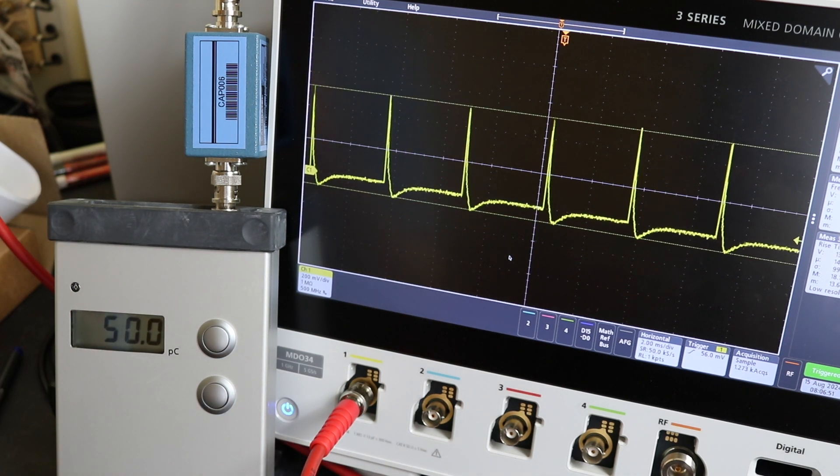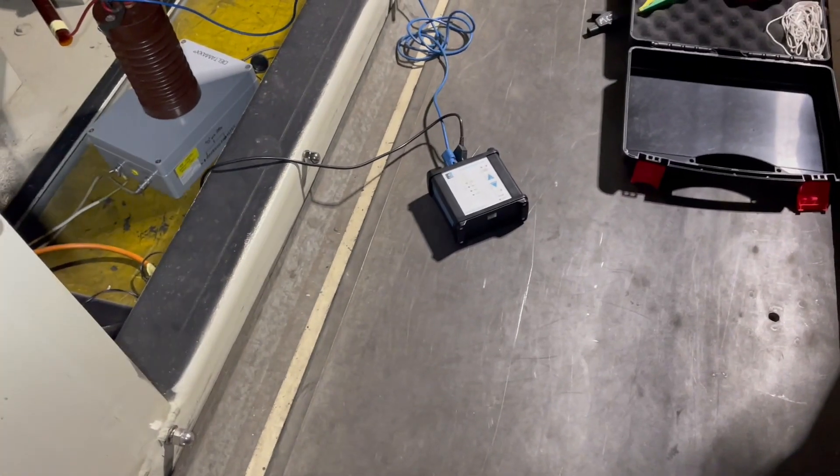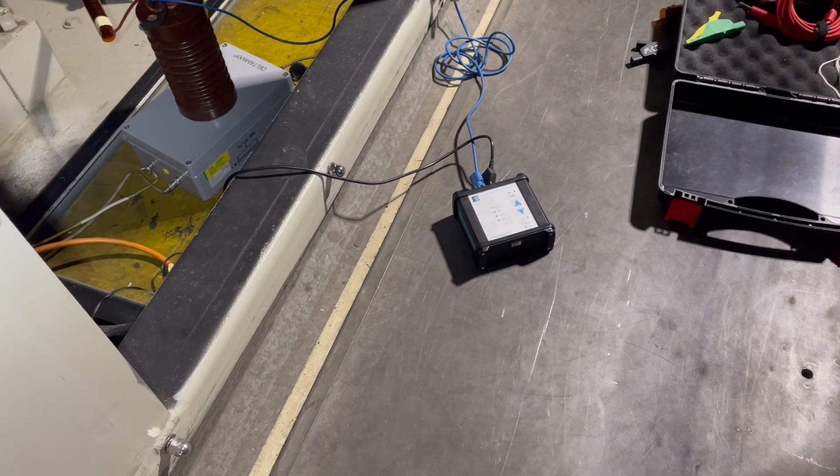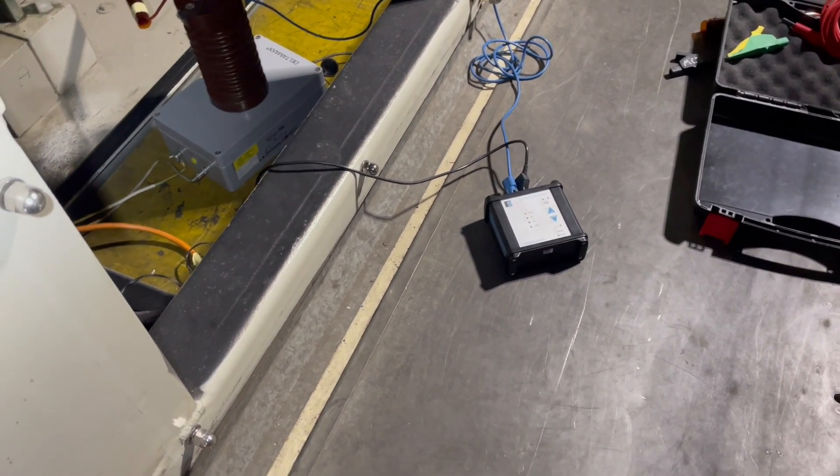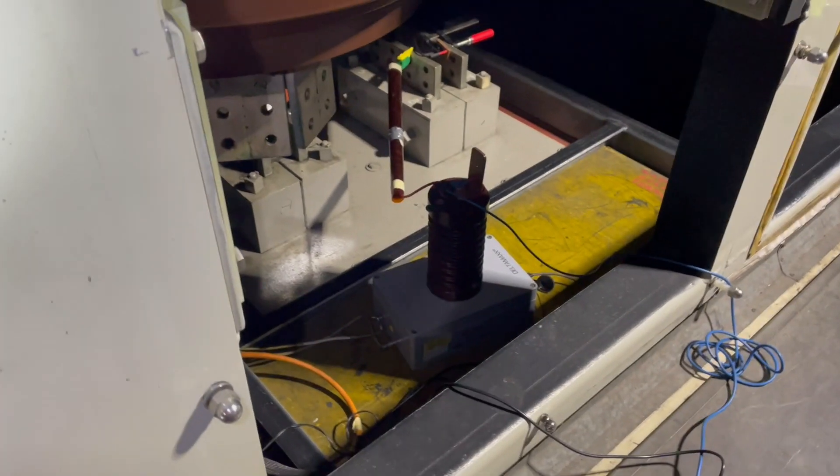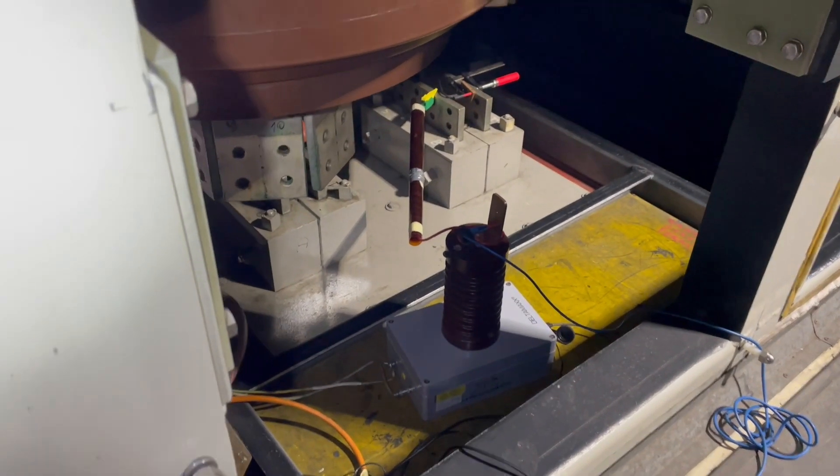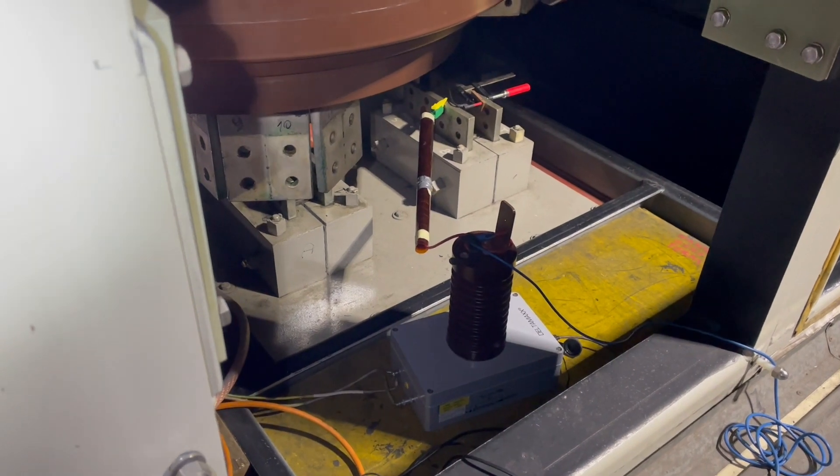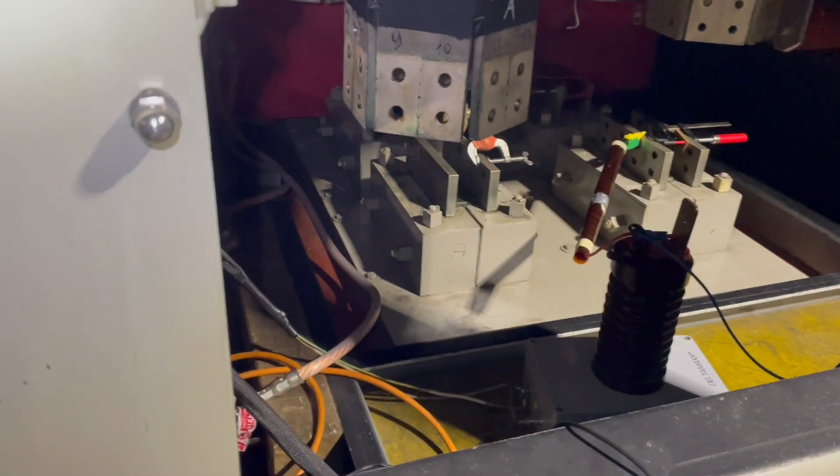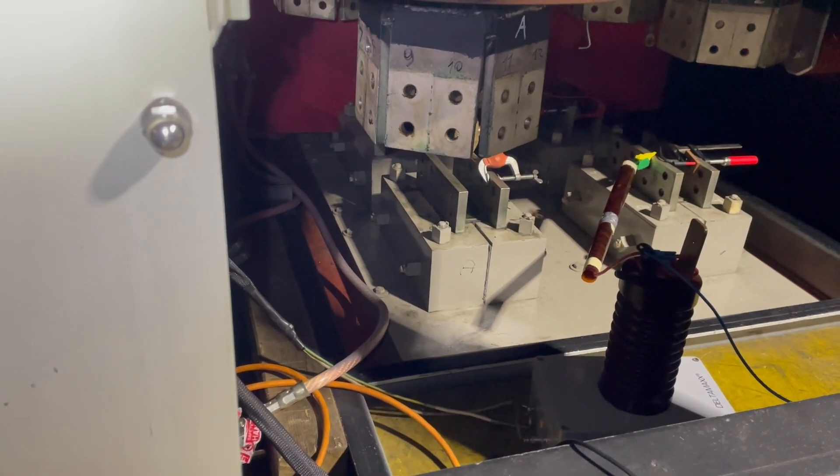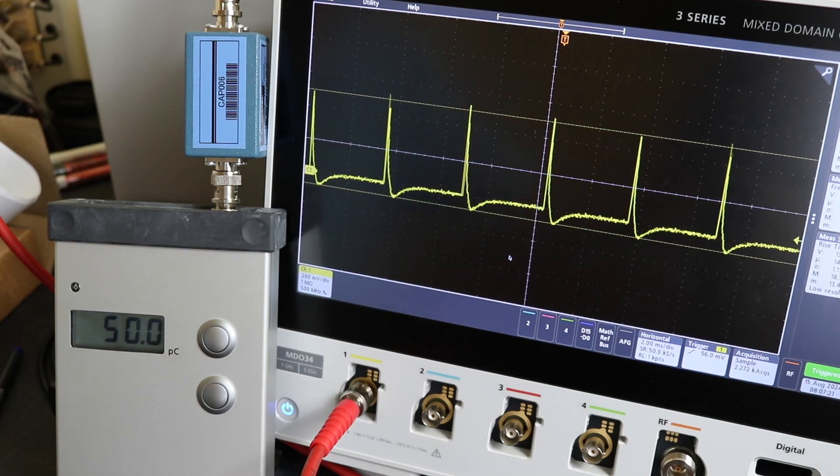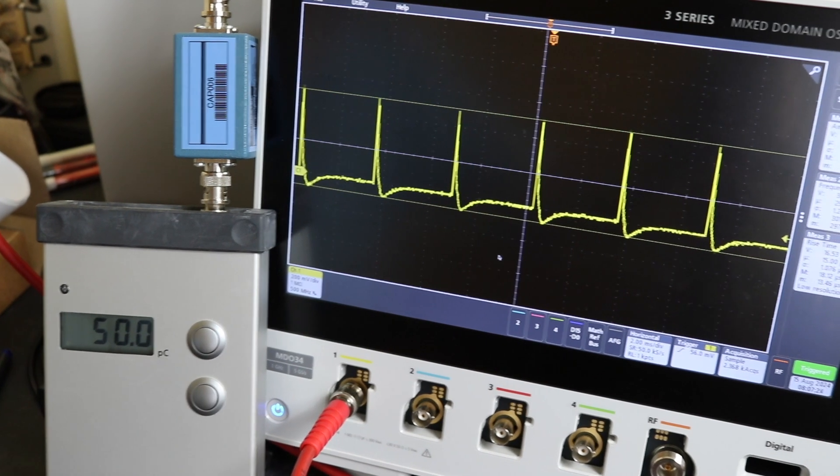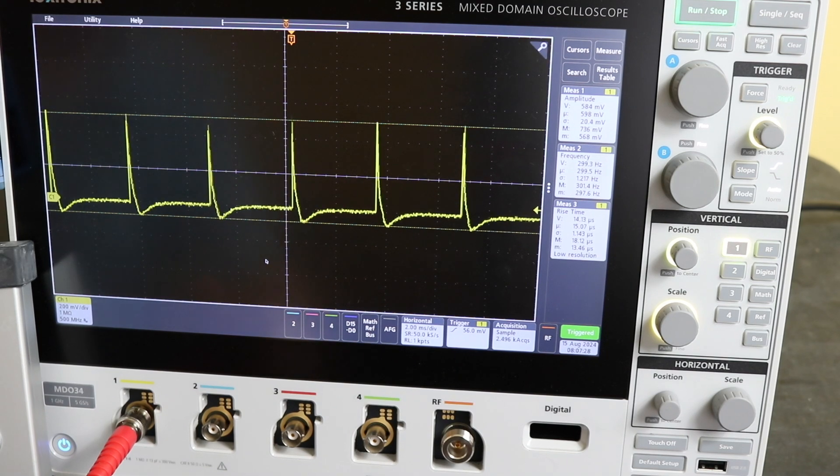This pretty much emulates what you'd see on a machine. I just put this little video snippet up here. This is an actual partial discharge calibrator connected up to a generator terminal. You can see the calibrator is a different unit to this one but the calibrator is there and you can follow it through onto the connection onto the actual generator terminal. By the side of that to the right is the actual partial discharge coupler which will be either 80 picofarads or one nanofarad usually. That's what this unit here is emulating. So I've got a similar test circuit for an actual generator there.